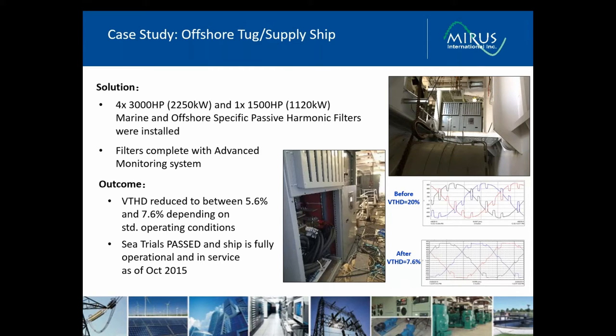So series connected passive harmonic filters were applied to each of four 3,000 horsepower propulsion DC drives and one 1,500 horsepower DC drive retractable thruster. The system voltage distortion was lowered to less than 8% under all operating conditions, resulting in an ABS compliant harmonic profile. The filters also substantially reduced the voltage commutation notching introduced by thyristor operation of the DC drives, which was believed to be a major contributor to the equipment failures. In addition, the built-in monitoring system offers early stage warnings complete with redundant safety controls and alerts. In compliance with the new ABS standards, the harmonic filter will disconnect the capacitor bank while maintaining operation should any problem occur with the capacitors.